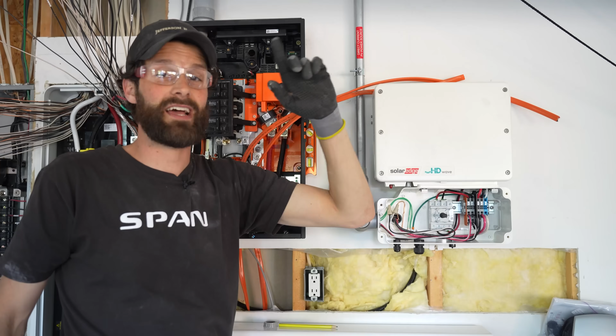Span also needs communication, just like the Tesla gateway, which is the brains of the Powerwall system. We'll have full monitoring and intelligence on all three platforms. SolarEdge gives us module level data, insights, and reporting, meaning every solar panel individually reports to the customer, to SolarEdge, and to our office so we can see in real time if there's a failure or fault. It'll flash a red X on the monitoring platform under the customer's name to draw our attention. We've got about 500 sites, but it prioritizes sites with outages. SolarEdge has a free app with free lifetime monitoring, and so does Tesla Gateway 2. Here we've got some CTs, current transformers, which aren't landed yet, so it's not plugged in.